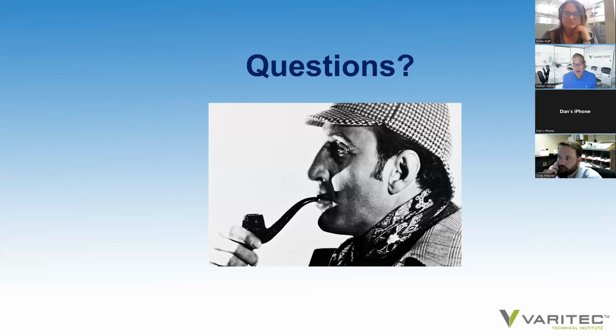That's an excellent question. Again, it depends on the building type of usage, what type of building humidity is being generated by occupants and building usage, sinks, restrooms, etc. Anywhere where there's open water to the environment. The best way to actually deal with that, depending on the building, is you're going to need some way during those drier times of the year in the winter of providing humidification or moisture to the space so you could control to 40 to 60%. Otherwise, you can see it drop below 40%.